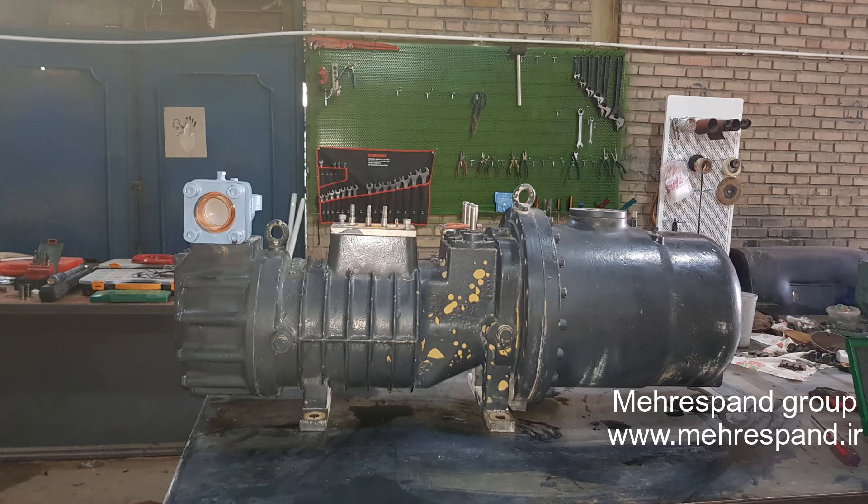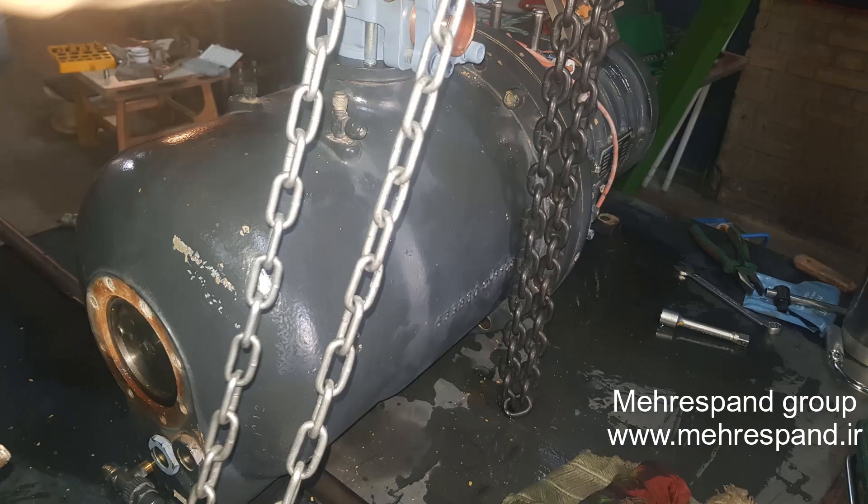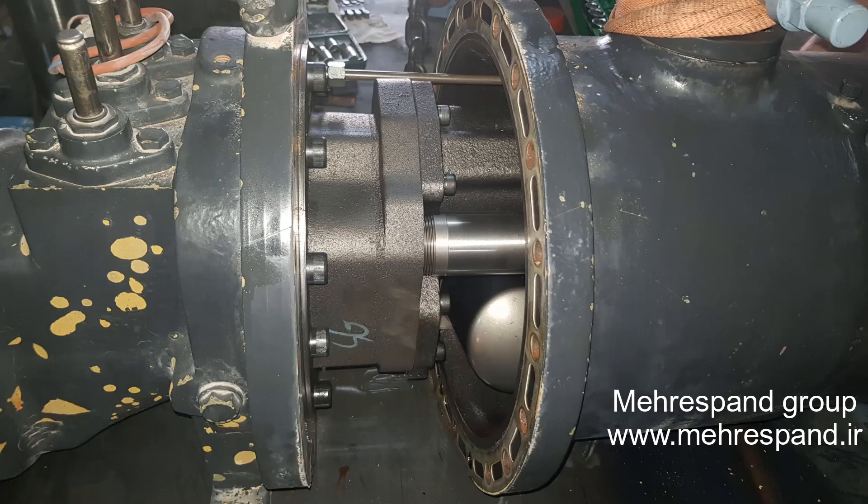In this video we are going to talk about the reasons for failure in this Refcomp screw compressor. This compressor was sent to Mehrespand workshop for taking high ampere and locking rotors, so the first thing that came to our mind was a mechanical problem.